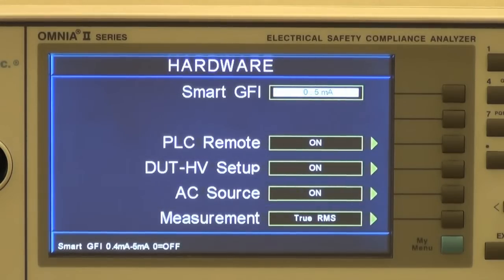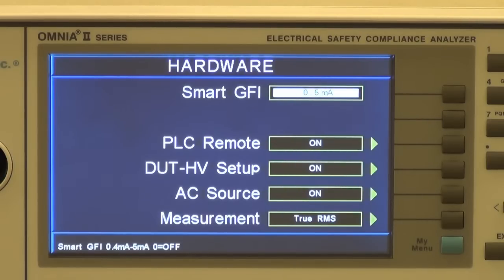If you have an 8207 or 8257 instrument, you'll have the option to set the internal 500 VA power source for the line leakage and functional run tests. From the hardware settings screen, you may turn the AC source parameter selection on or off by pressing the AC source soft key. When the AC source is turned on, the 500 VA power source is available for use during the line leakage and functional run testing. An additional set of parameters will be available in the run and line leakage parameter settings screen.